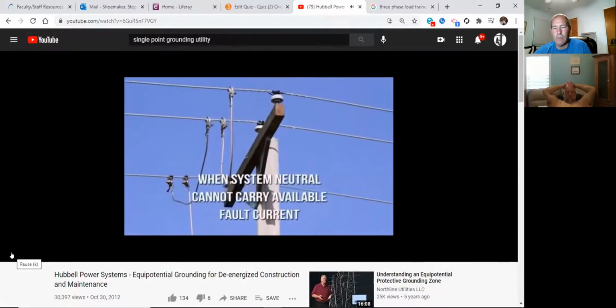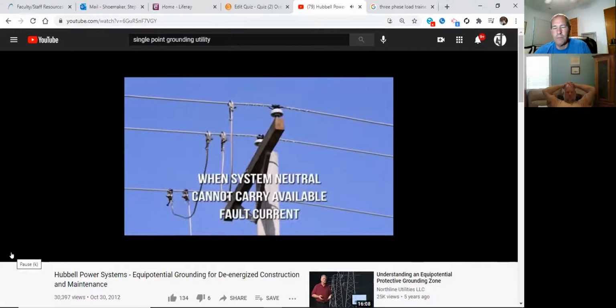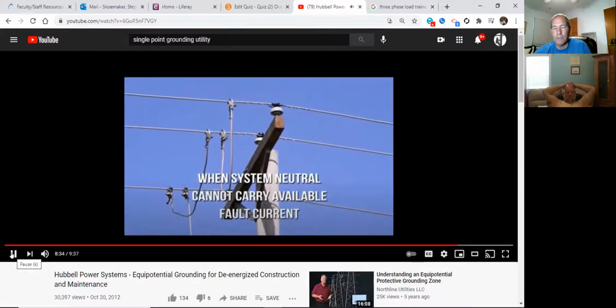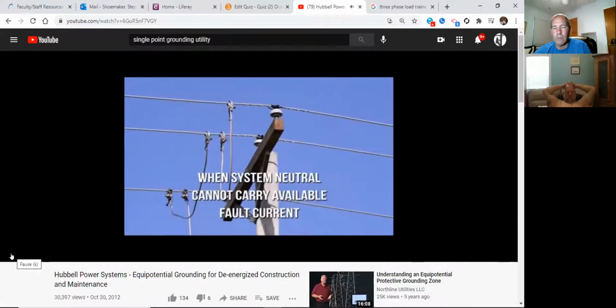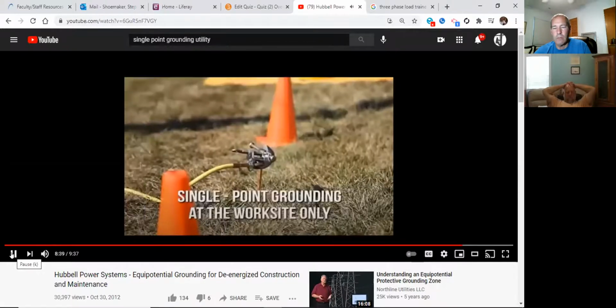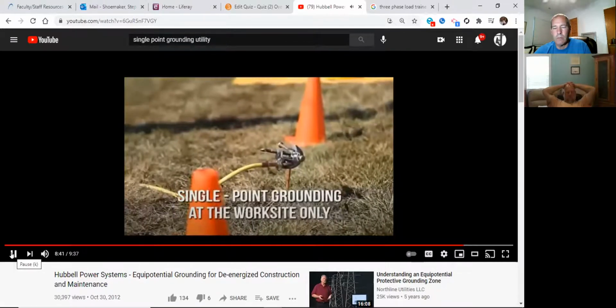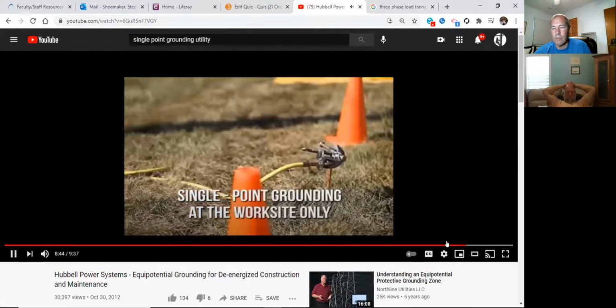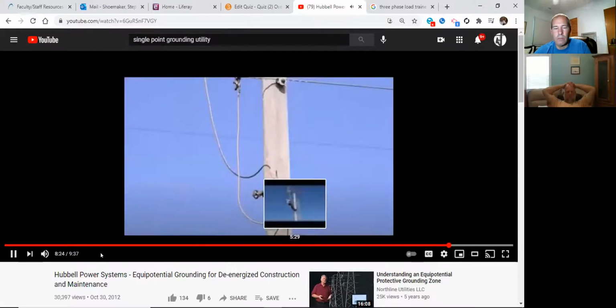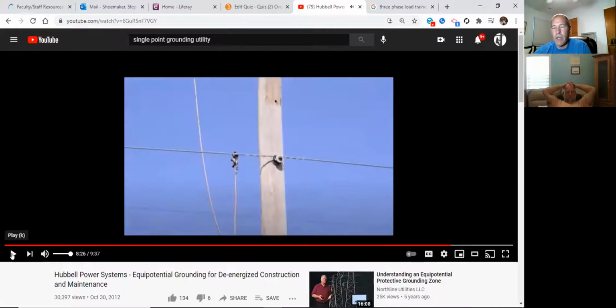This alternate setup takes no more leads than the first way shown, with a lead from the cluster bar to the neutral and another from the cluster bar to the phases. Another way to establish an equal potential zone employs single point grounding at the worksite only. Connect one lead from the cluster bar to the neutral. So what's he saying here when he says if the neutral is unable to carry the fault current? What does he mean by that?